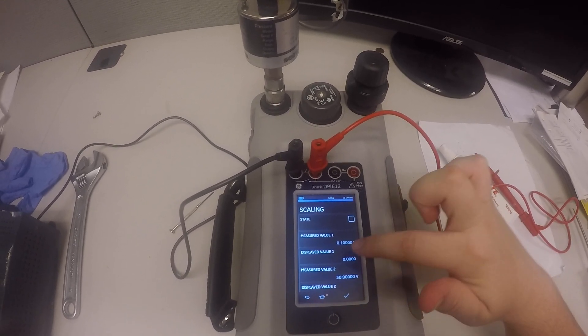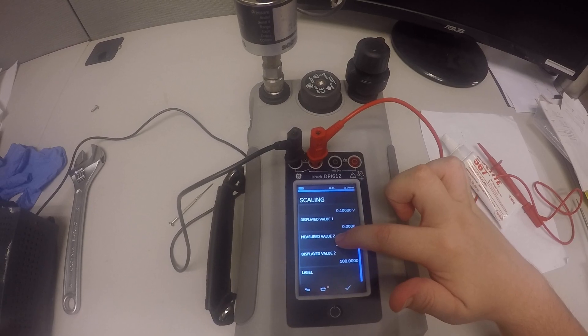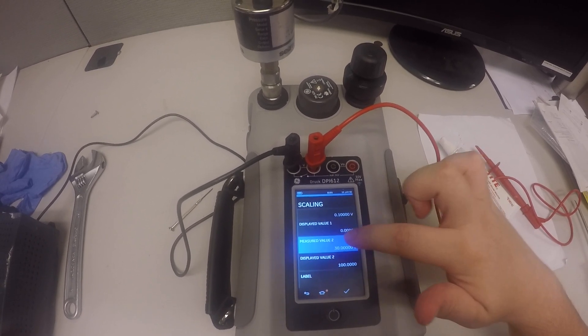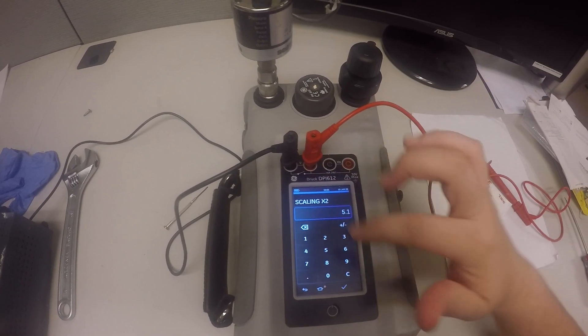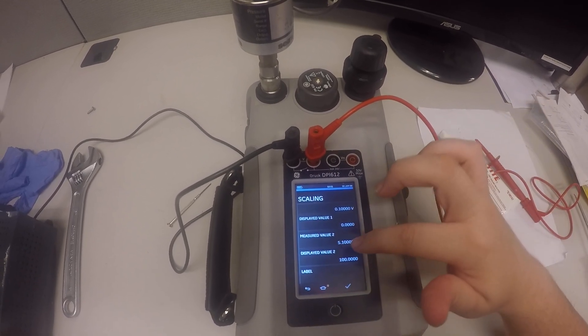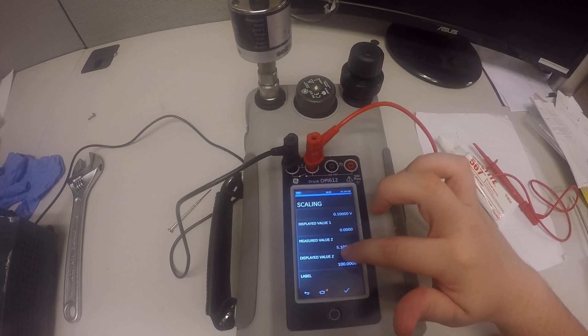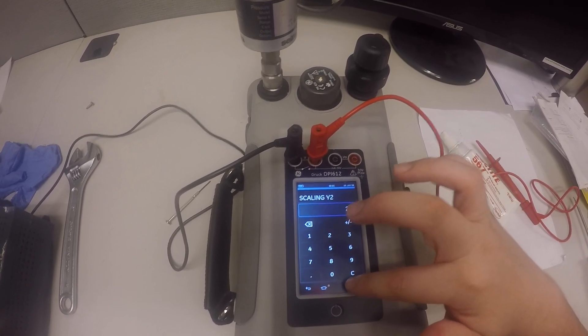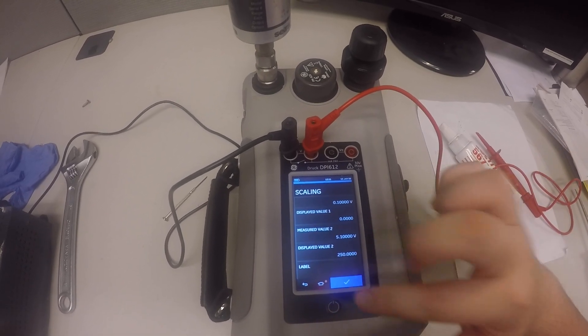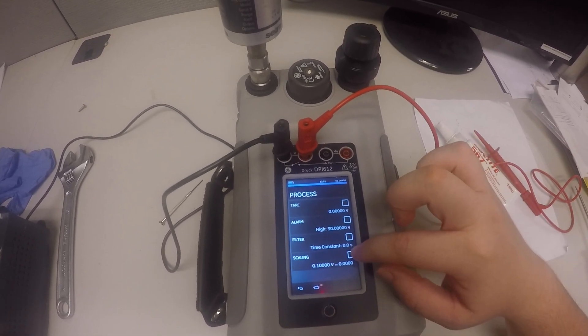0.1 volts corresponds to 0 PSI. And Measured Value 2 is going to be 5.1 volts. That corresponds to a pressure of 100 PSI, since that's the max on the range of this transducer. Now we hit that check mark.